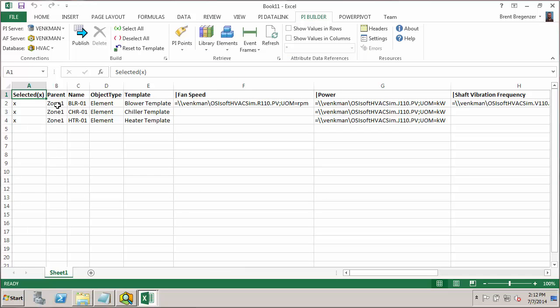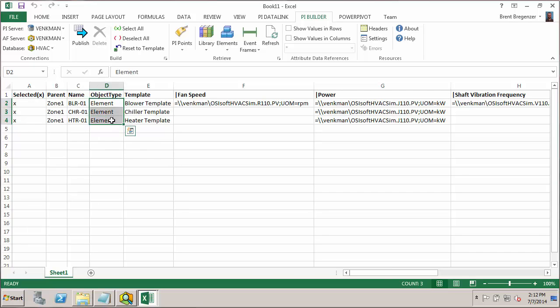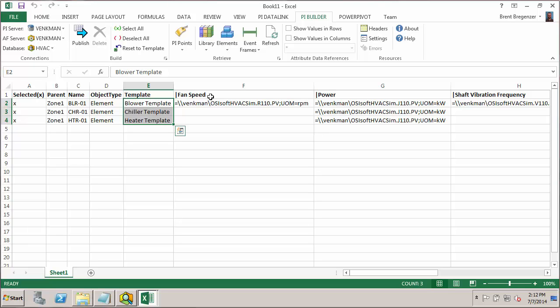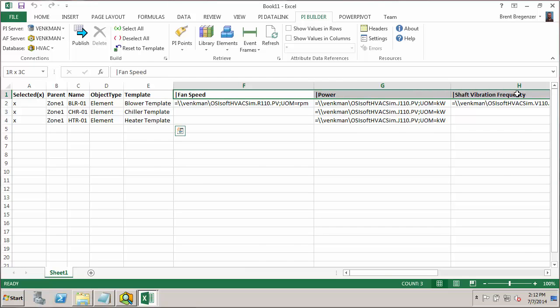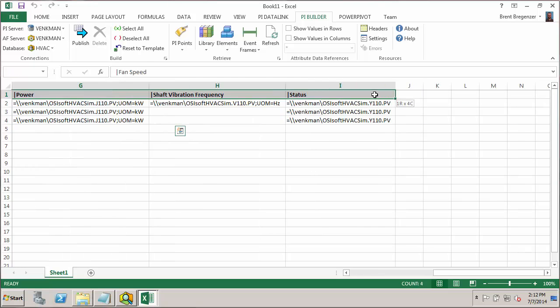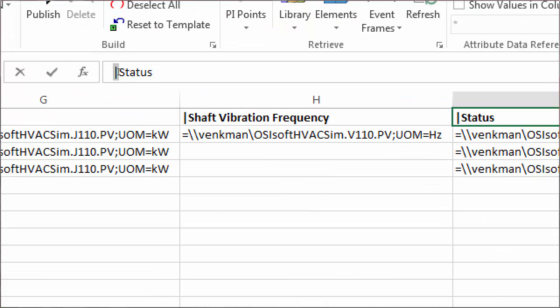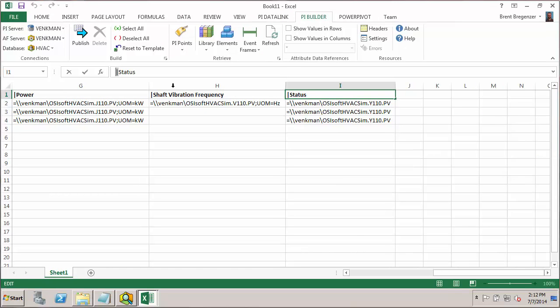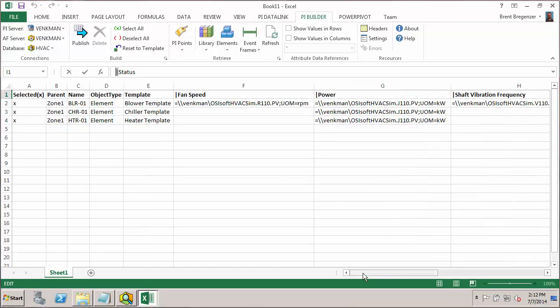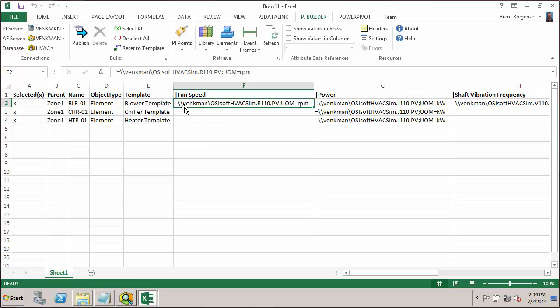So here you'll see we have the parent is zone 1. Here are my element names that we've built. The object type is element, and it tells us which template those elements are built off of. So all those fields will be key when we want to build new elements from the spreadsheet. And the next thing you'll notice is we have these other columns. These have attribute names as the column header. The way I know their attribute names is because of this pipe symbol in front of the attribute name. And then we'll see some particular syntax here for the builder. You'll see that there's an equal sign in front of each of these tag names. And this is so that the AF builder knows to interpret any string that comes after the equal sign as being something that should be plugged into the configuration string for the attribute rather than the value of the attribute.